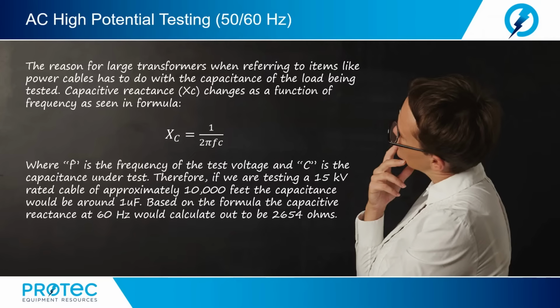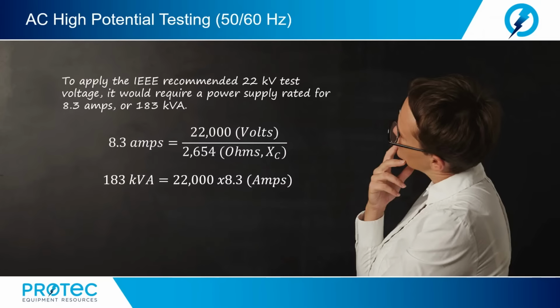Now, based on the formula, the capacitive reactance at 60 hertz would calculate out to be 2,654 ohms, as we can see in the calculation here. All right, now, to apply the IEEE recommended 22,000 volts of test voltage, it would require a power supply rated for 8.3 amps, or 183 kVA. To find this, we simply take 22,000 volts divided by the capacitive reactance in ohms, and we see that we get 8.3 amps that the power supply would need to provide.